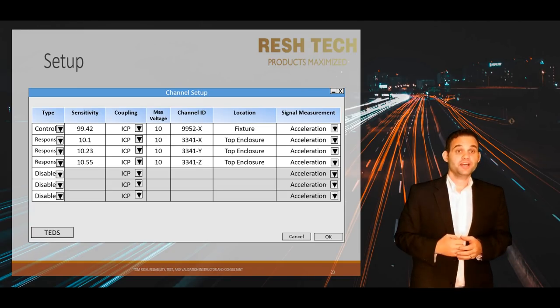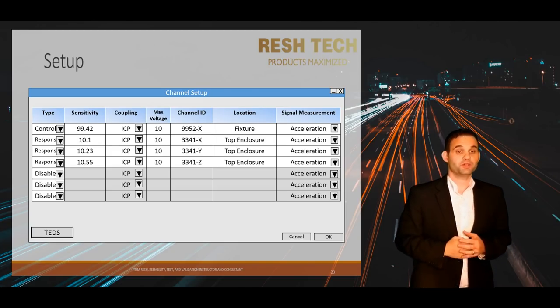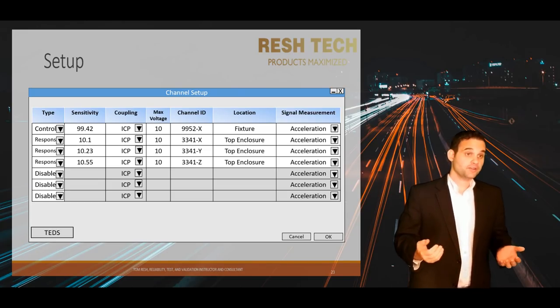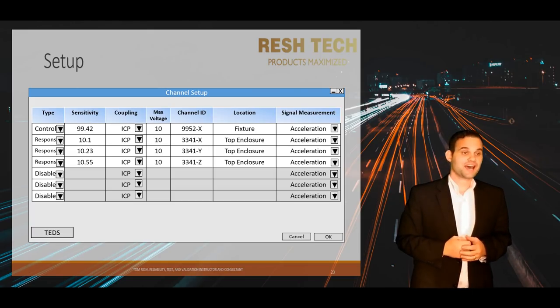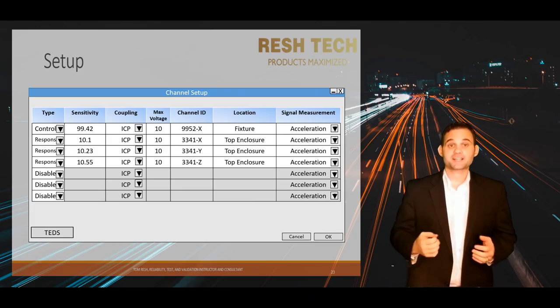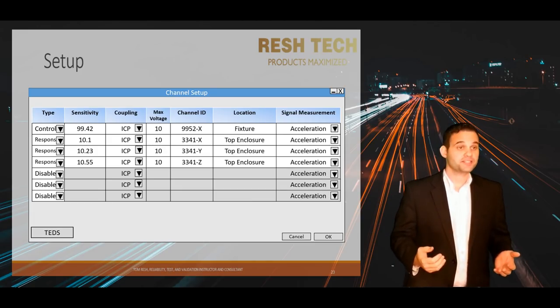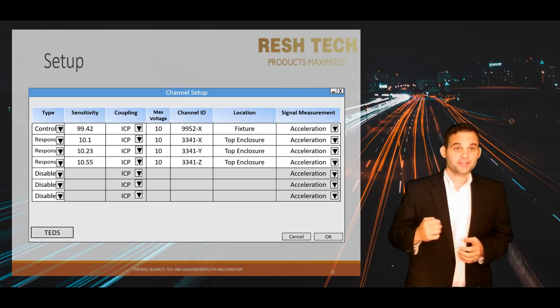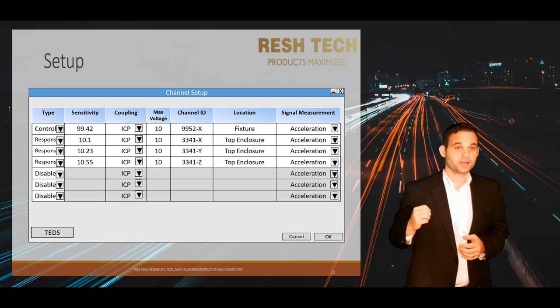The next parameter is sensitivity. This value can be found on your voltage mode accelerometer's box. Check your calibration data on your accelerometer to make sure you are not using a sensor that is out of calibration. The next column is max voltage, which can be found on your accelerometer manufacturer's data sheet — this is the maximum voltage range for your accelerometer.